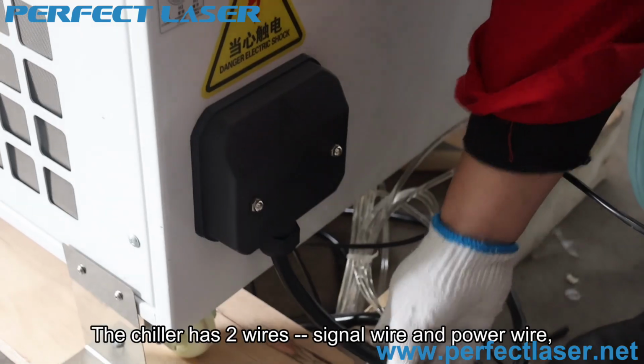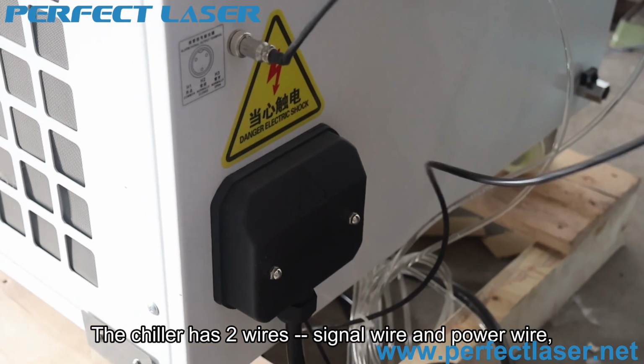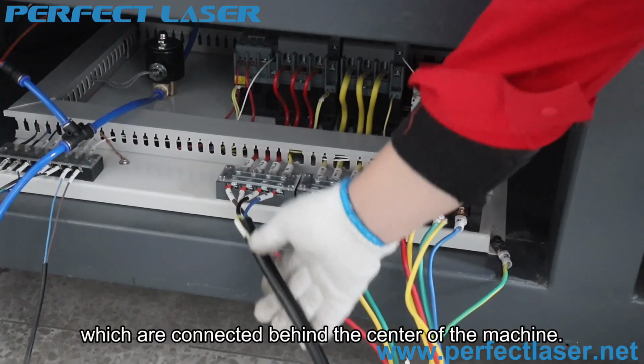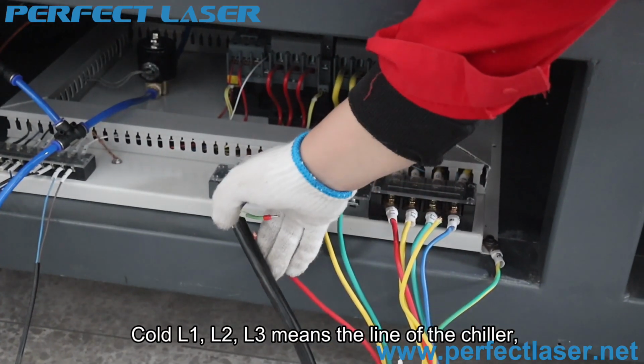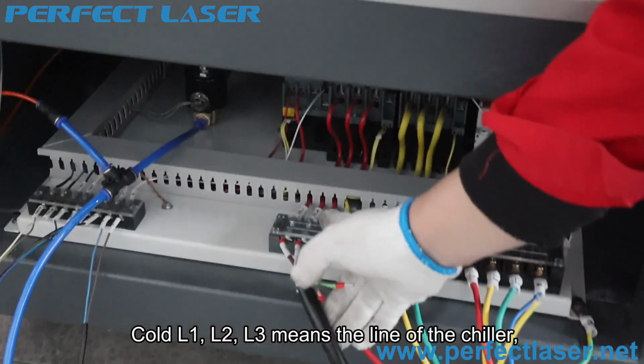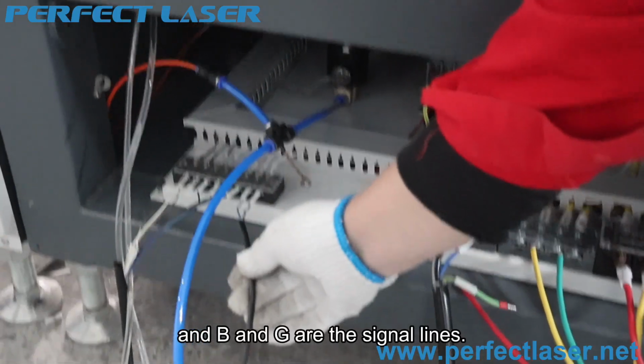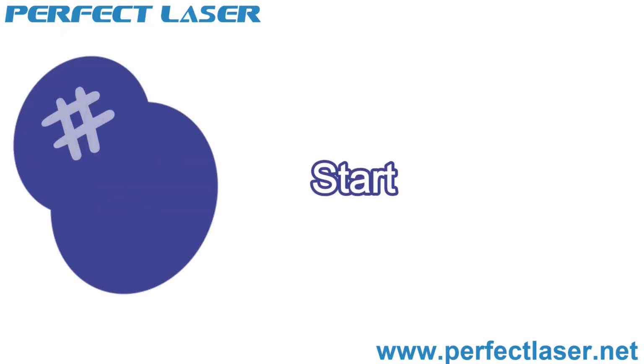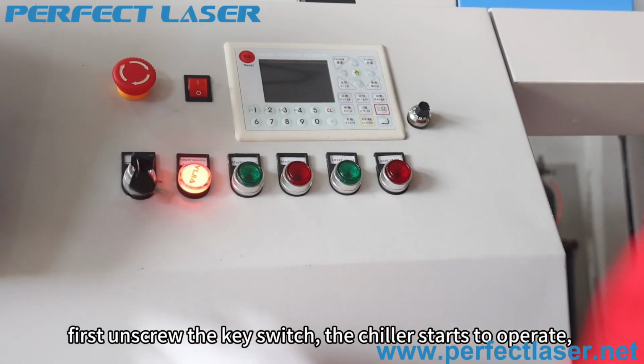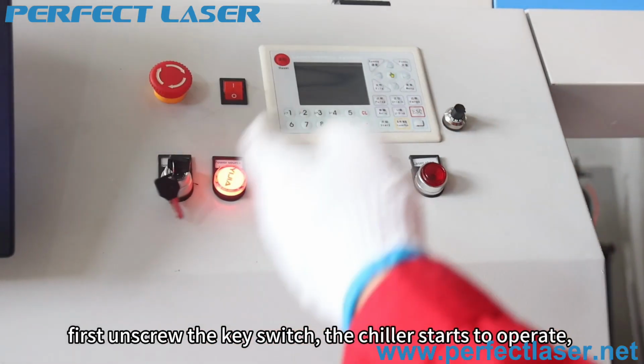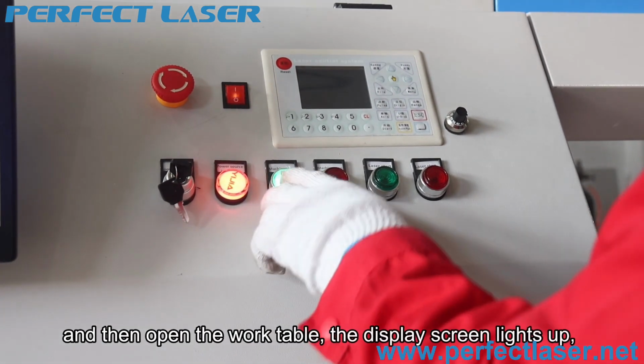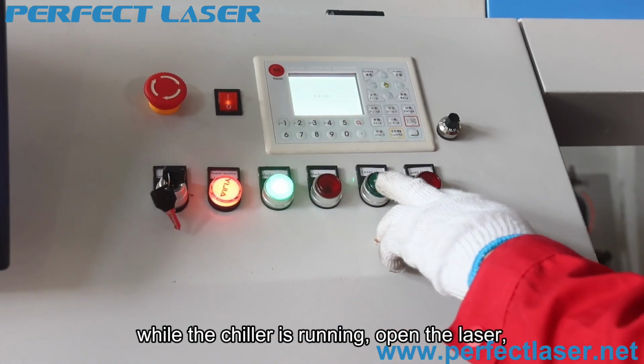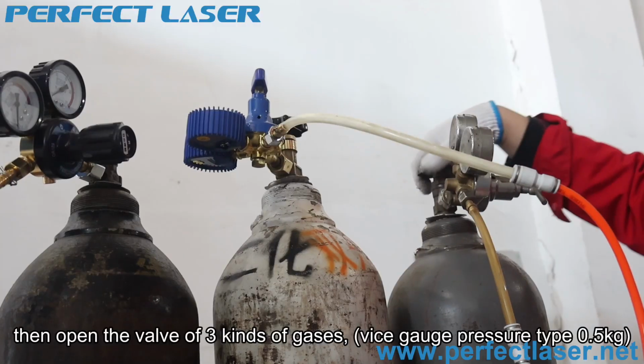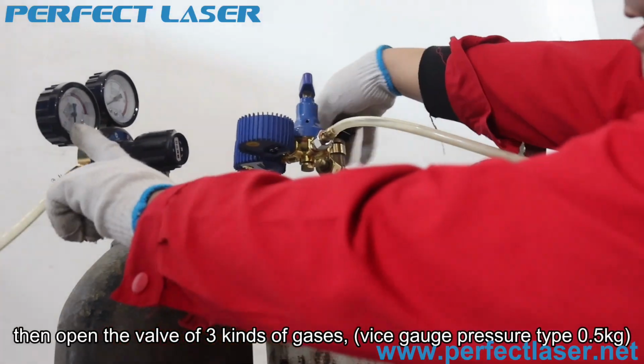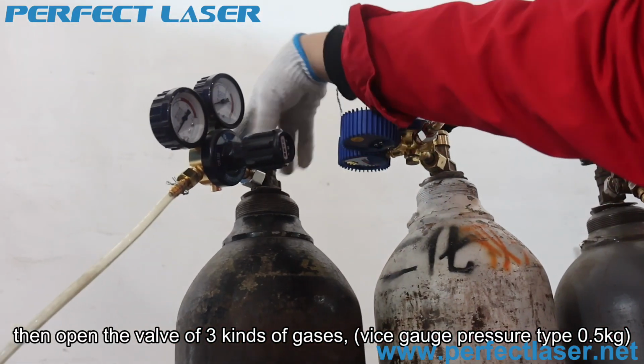The chiller has 2 wires, signal wire and power wire, which are connected behind the center of the machine. Cold L1, L2, L3 means the line of the chiller, and B and G are the signal lines. Start. First unscrew the key switch, the chiller starts to operate, and then open the work table. The display screen lights up. While the chiller is running, open the laser, then open the valve of 3 kinds of gases, vice gauge pressure type 0.5 kilograms.